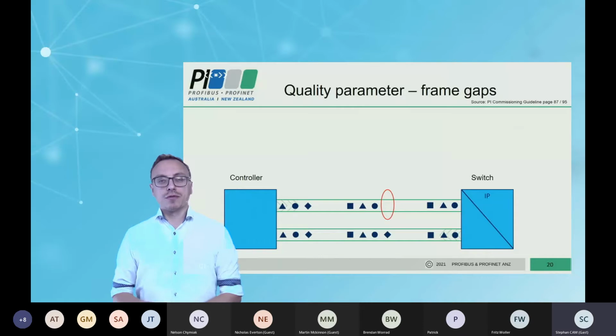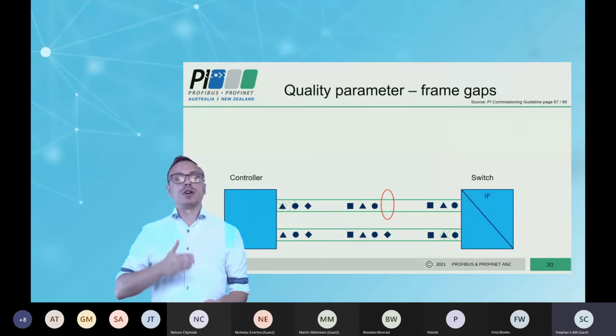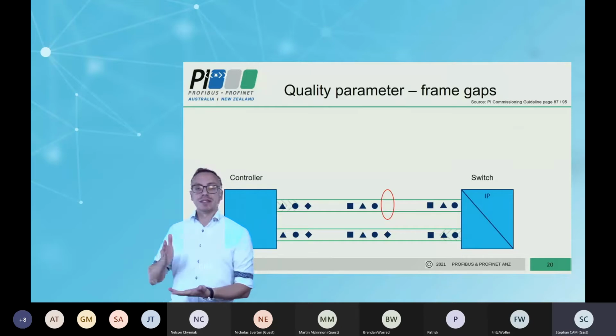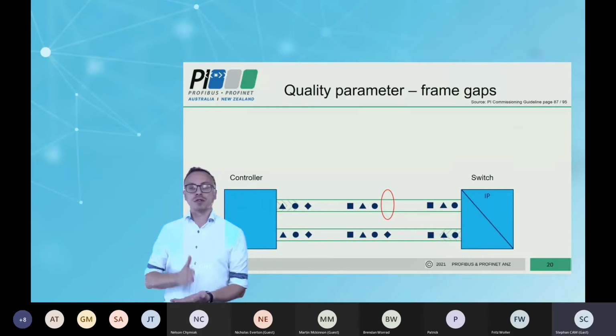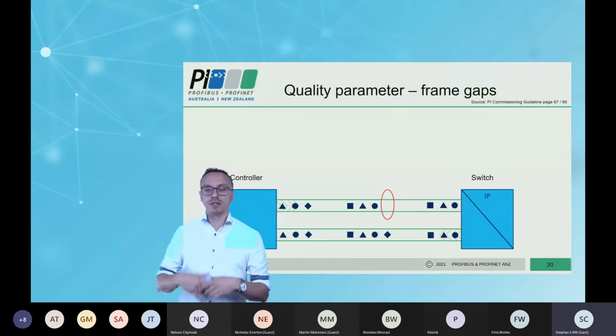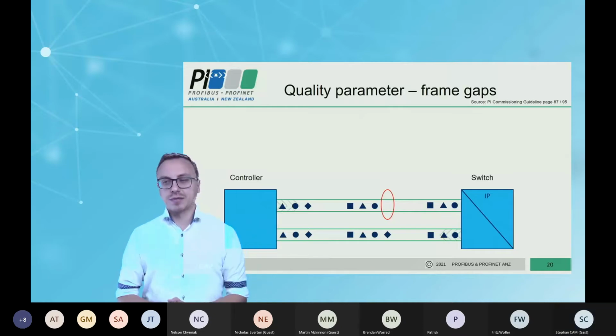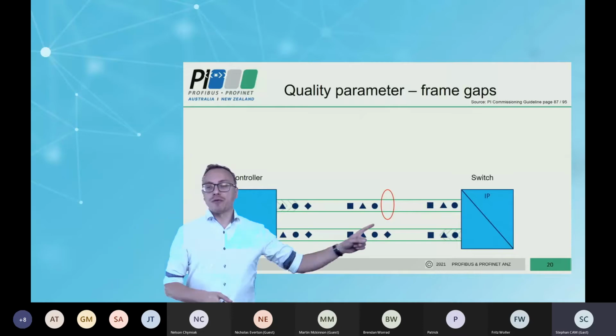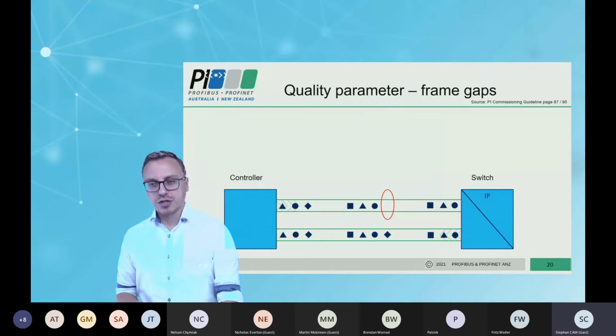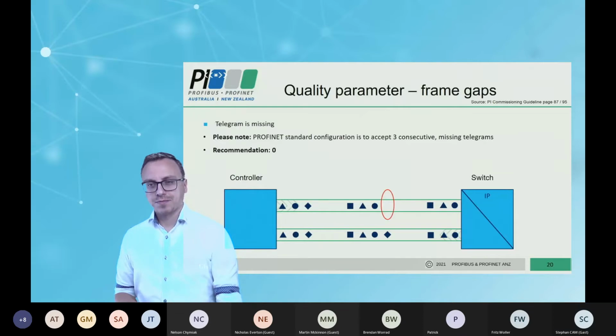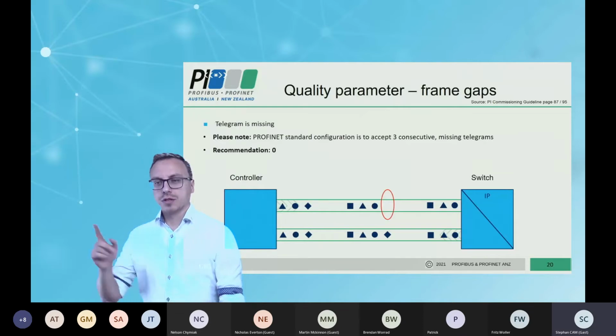So now, if you remember your watchdog, if you have 3 missing frames in a row, your plant will stop, or you go into a safety mode, so a safety stop. So if you have 3 frame gaps in a row, your plant will stop. Okay, this is the same as you have it in the slides. As I said, the common watchdog configuration is 3. So if you have 3 missing frames in a row, you get this stop.